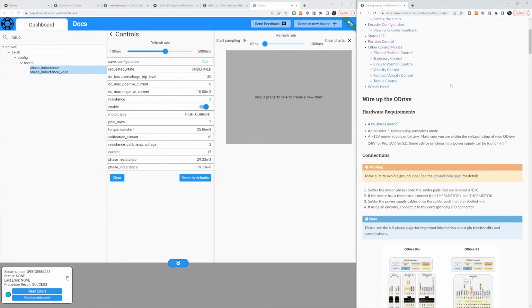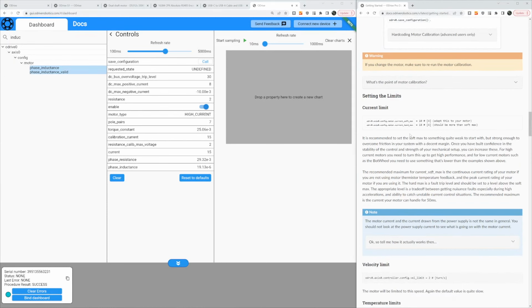All right, well, setting the limits. So this is the current limit for the motor. Notably, the motor current is not the same as the DC battery or power supply current. Usually the motor current can be much higher. You can read more about it here in this area of the documentation. And it says here recommended to set something quite weak to start with. So that's what I'm going to do. It's always good to start low and turn it up when you have some confidence.